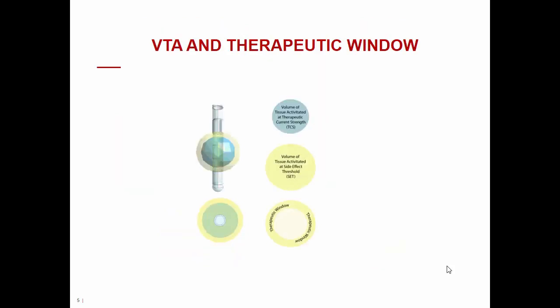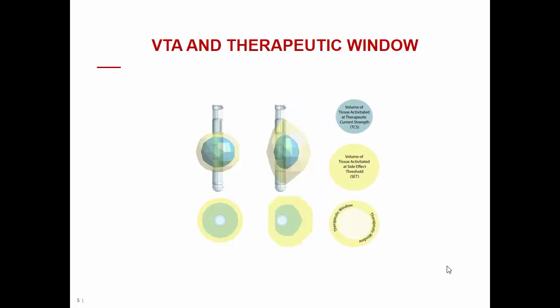With these concepts in mind, we can move into the core of programming: understanding differences in therapeutic windows. The therapeutic window is the difference in stimulation intensity between the therapeutic current strength — the minimal stimulation intensity needed to achieve complete benefit — and the side effect threshold, the stimulation intensity sufficient to cause persistent side effects. Directional programming allows creating completely different VTA shapes, resulting in completely different therapeutic windows compared to omnidirectional programming.